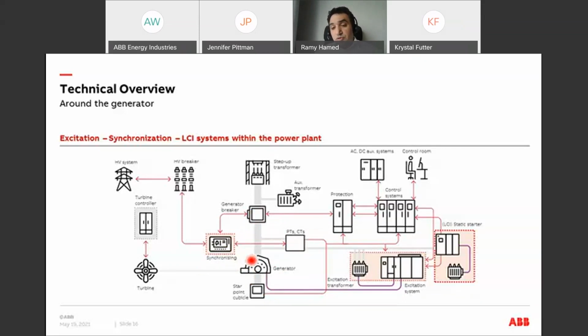The other component that we wanted to touch on today is the LCI, or the static starter. The static starter will be needed in some of the applications in the power plant, for example, the gas turbines. One of the issues with the gas turbines is that they cannot start on their own. They need a starter to reach a certain speed to be able to be fired and provide torque to the system. So to start the gas turbine, we use the generator as a motor, and the motor is started with the LCI, which is basically a variable speed drive for the synchronous motor.